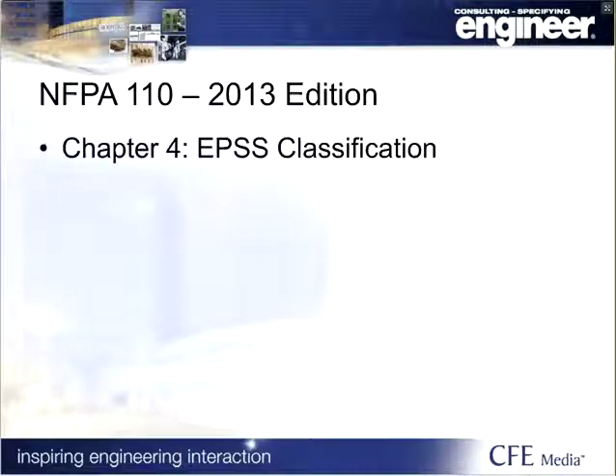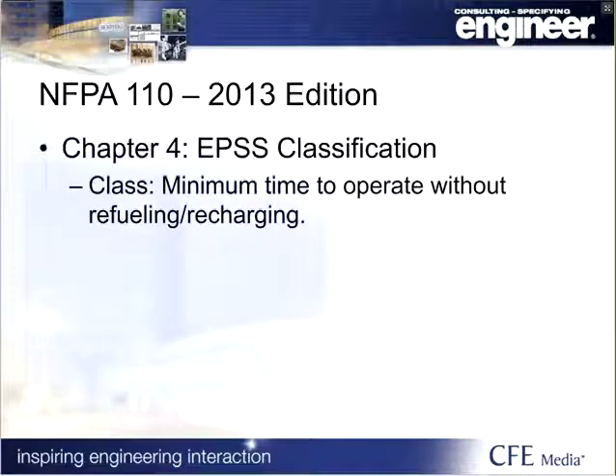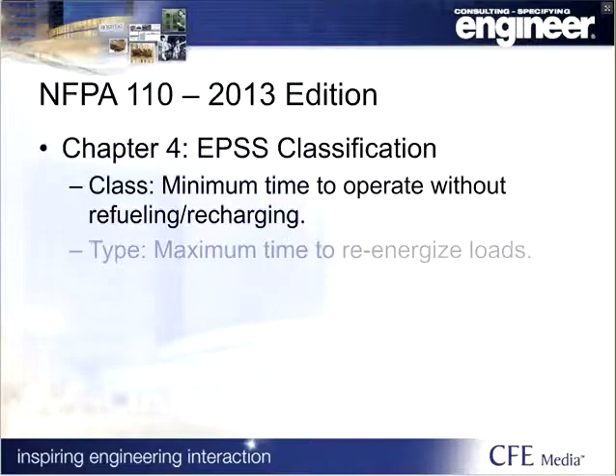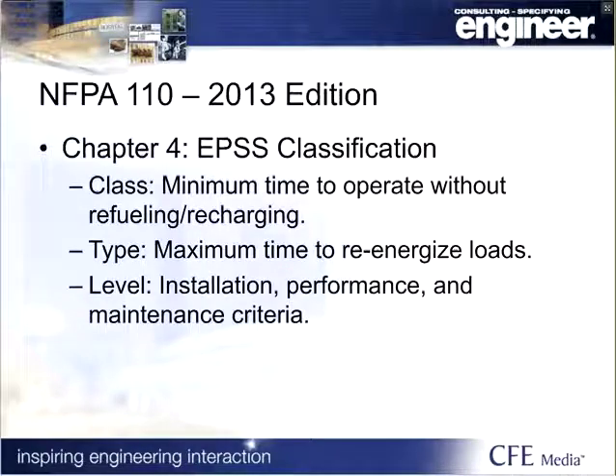EPSSs are classified using 3 performance and reliability gauges. Class is defined by the minimum time the generator system needs to operate continuously without refueling. Type dictates the maximum time allowed to pass before loads must be re-energized. And the level provides criteria for installation, performance, and maintenance, as well as testing requirements.